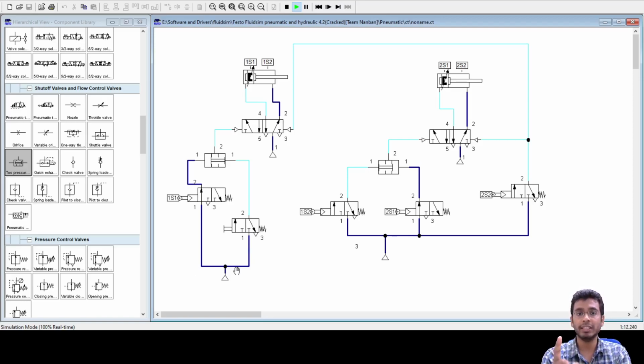That means two cylinders doing two works, maybe any other work, all combined. Similarly, if you replace this with a selector switch, then of course you can do n number of cycles. In the next step you can also place counters to count the number of cycles. Say you want to execute this for 10 cycles. There is a counter which counts. The moment the counter receives a preset value of 10, this entire circuit would stop.